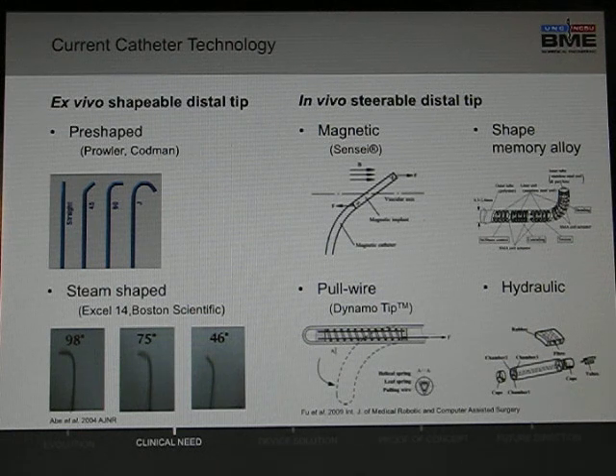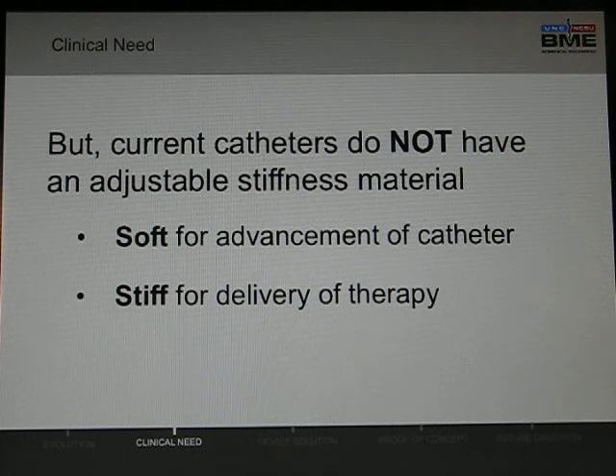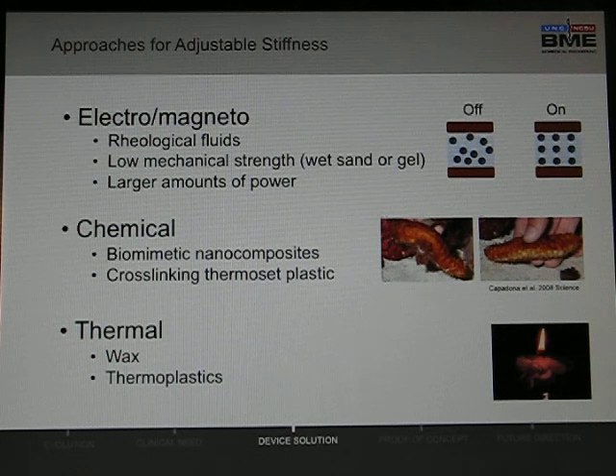Most importantly, none of these catheters has an adjustable stiffness material. It is important that the catheter is soft for advancement and on a flip of a switch become stiff for delivery. Here are a few approaches listed to adjust stiffness. Electromagnetorheological fluids have particles which, when large amounts of power are applied, can align, resulting in the fluid's apparent viscosity changing. It can go from a consistency of something like water to that of wet sand or gel.